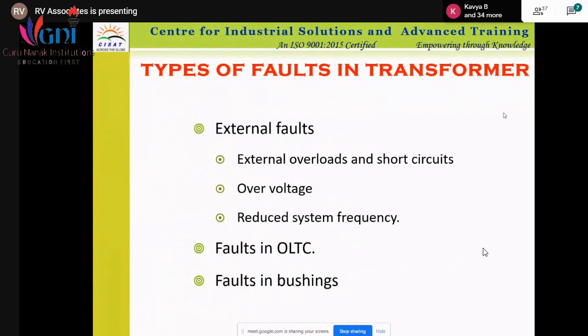Then there is a fault in the OLTC, faults in bushing. Normally, this last one, the fault in bushing, is a very common thing in industrial transformers or the heavy transformers. It can happen that after maintenance, if proper fitting has not been done, then there may be a failure in the bushings, and this is one of the widespread failure areas in the transformer. We can treat it as improper maintenance or improper fitting.